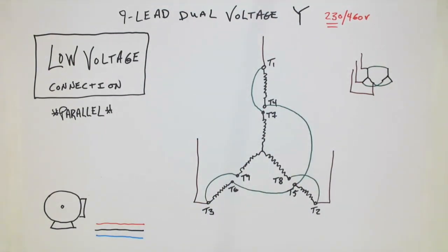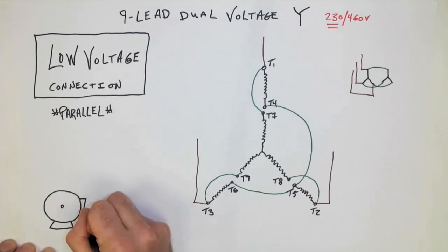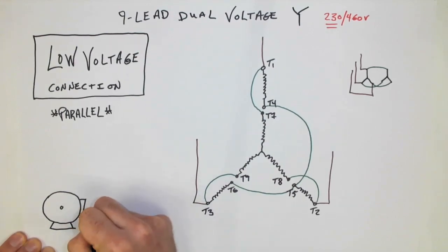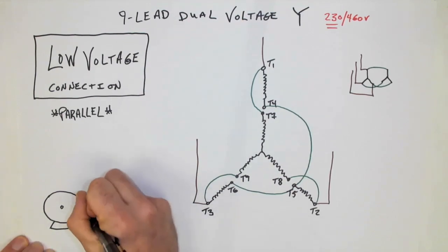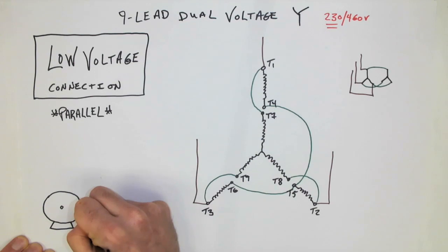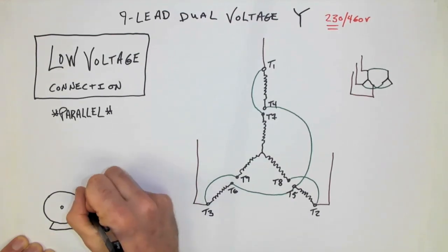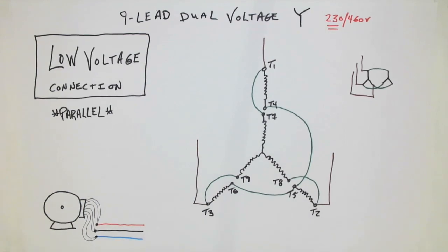Again, what this would look like in the motor junction box is very similar. We're going to have not only one wire connecting the line conductor to T3, but also T9. So there are 3 wires that would be connected together under a single marette: 1, 2, 3. And then we'd have the same thing for the next line: 1, 2, 3. And finally, 1, 2, 3. Now, what else do we have?